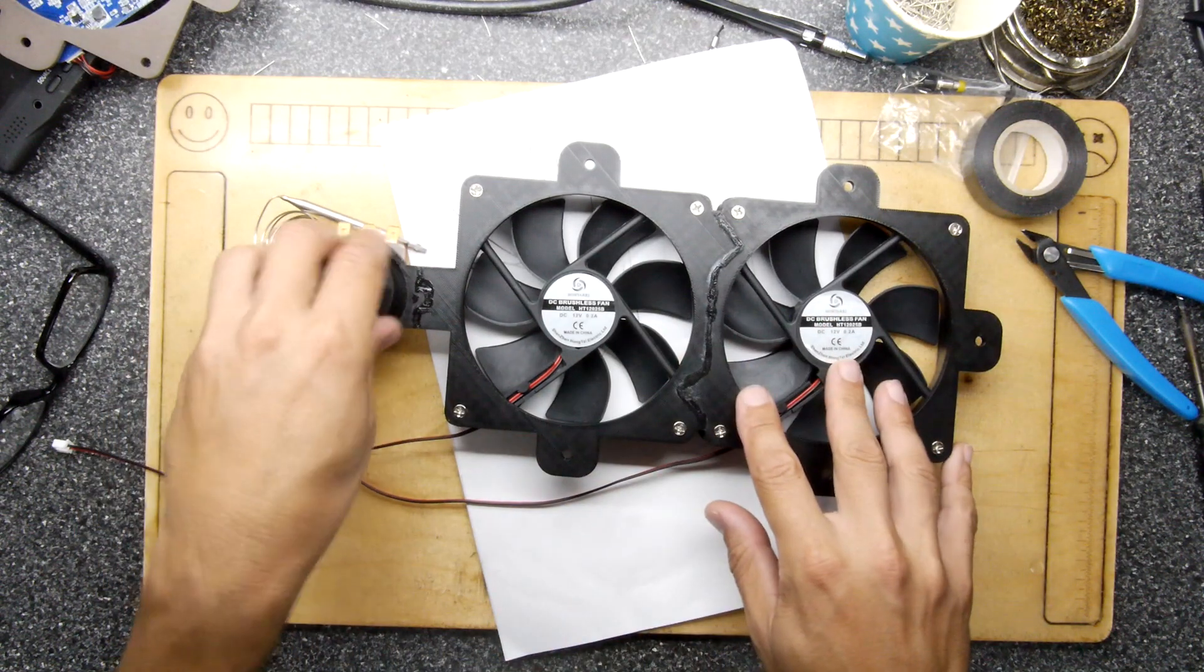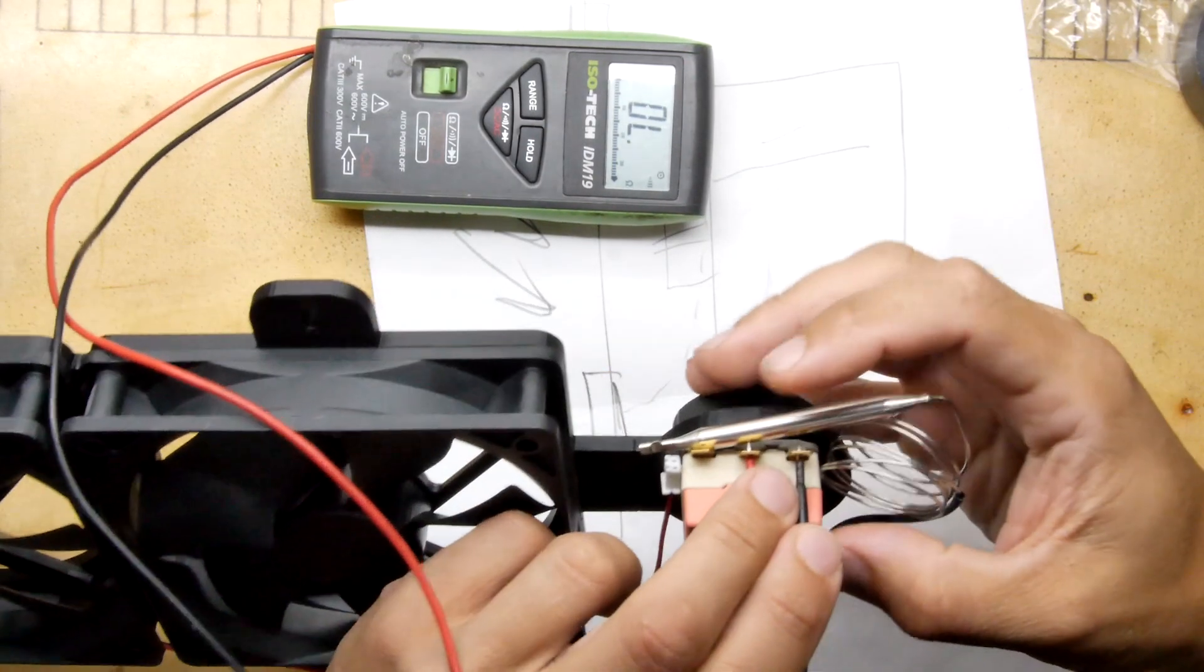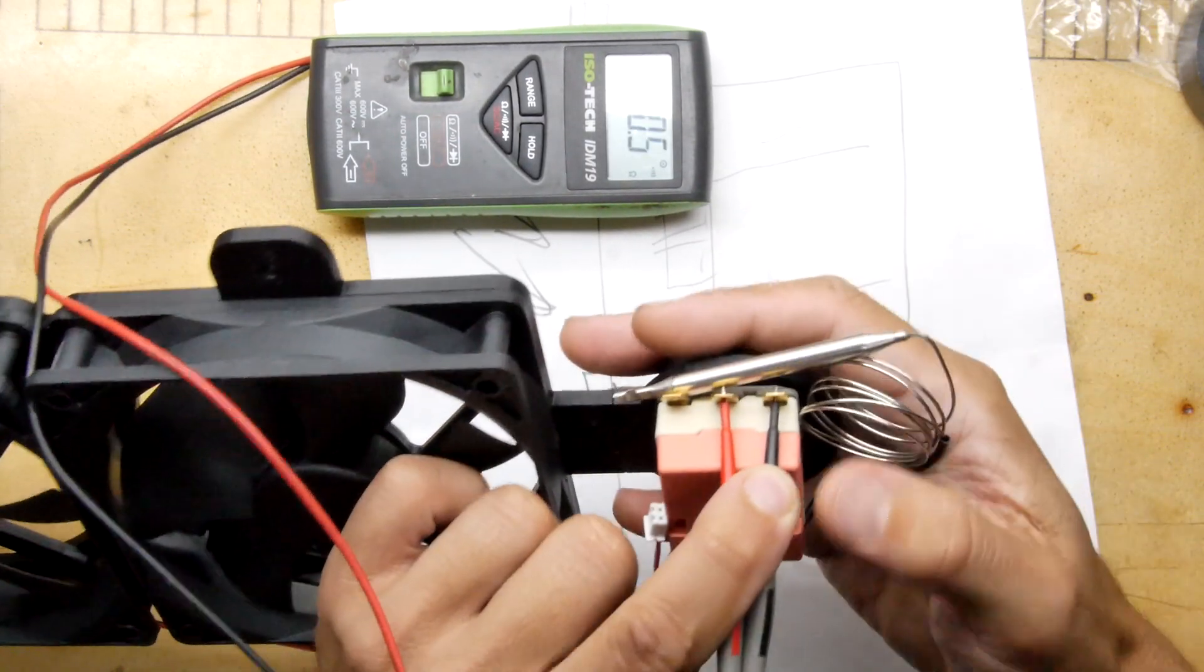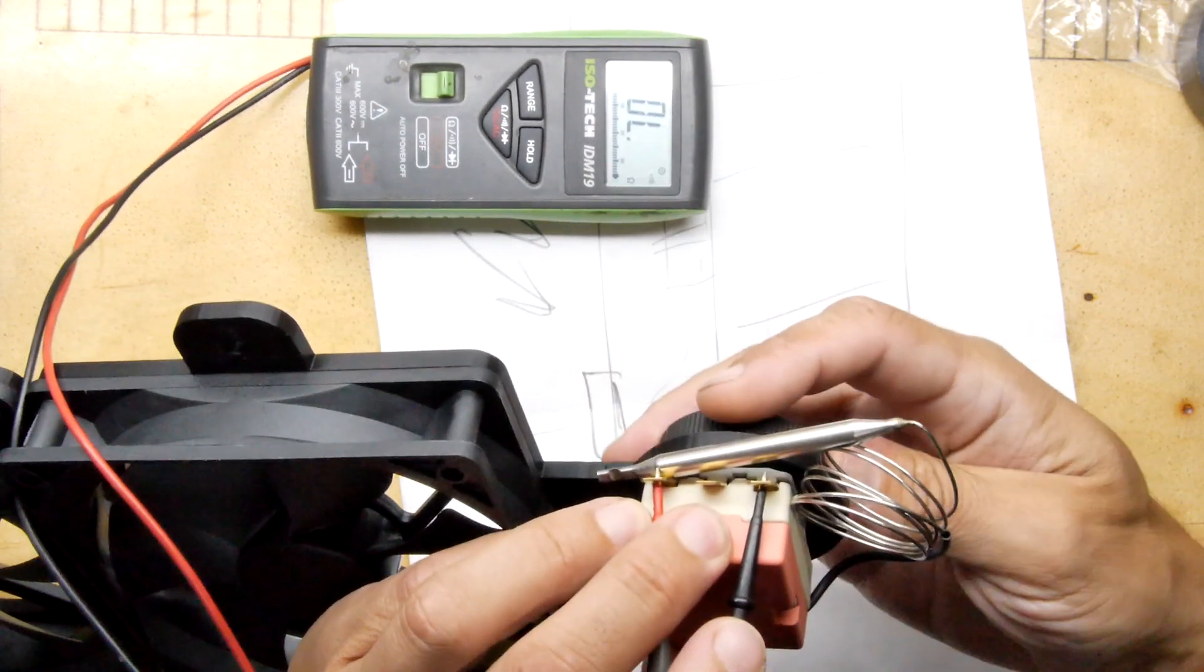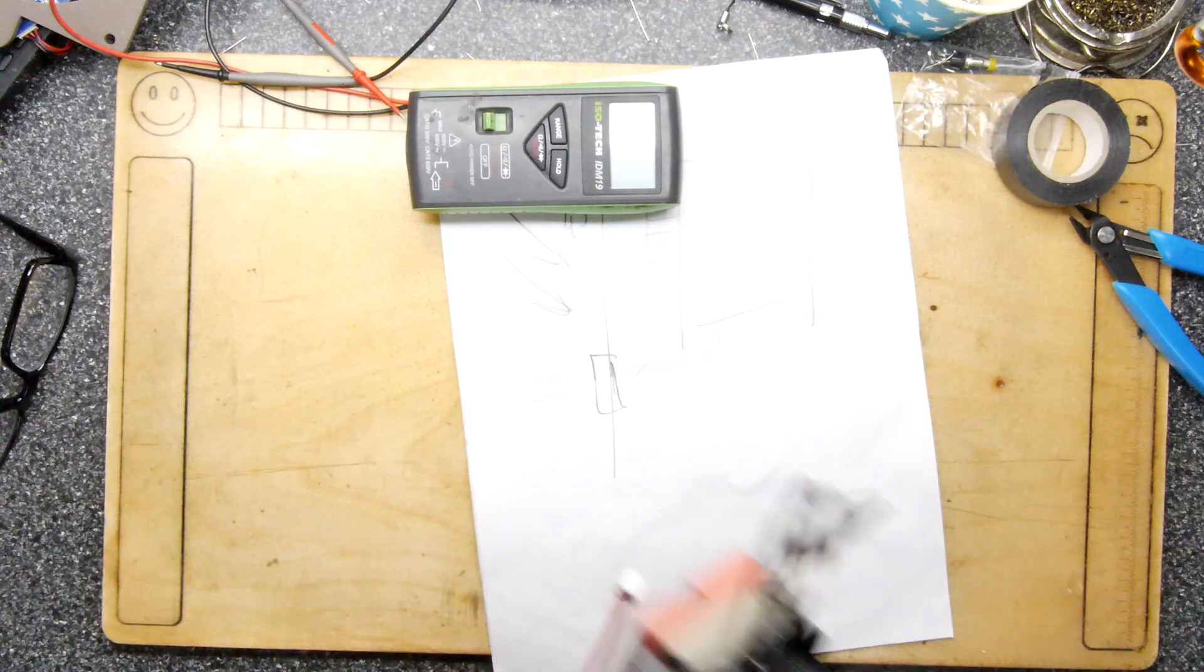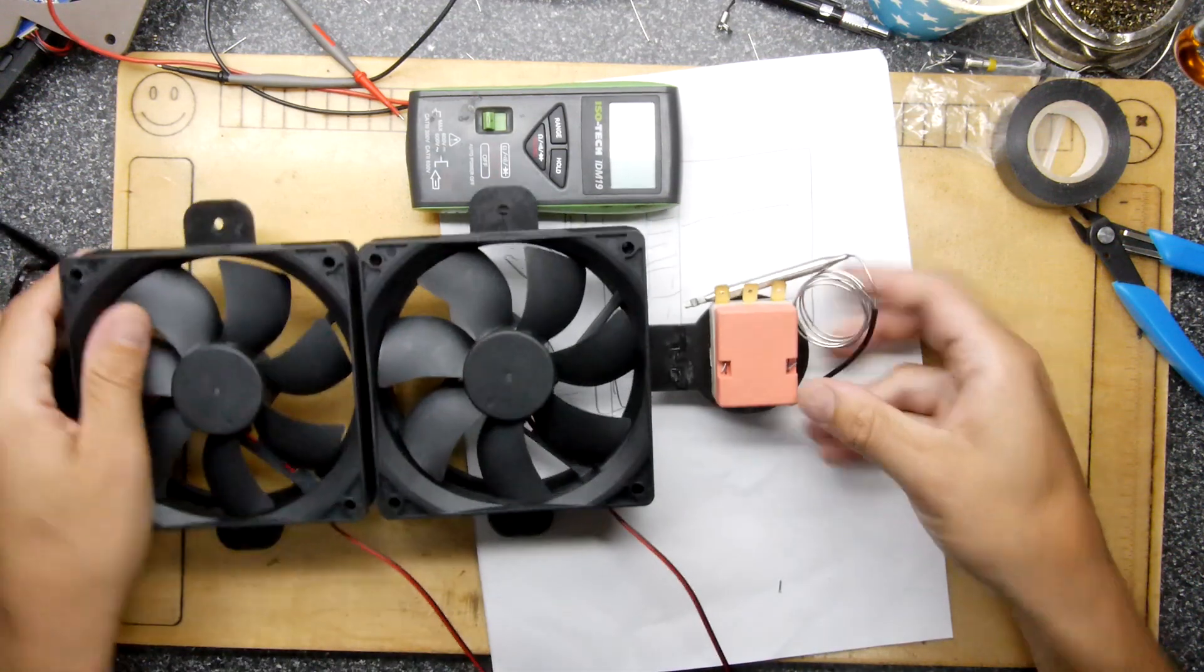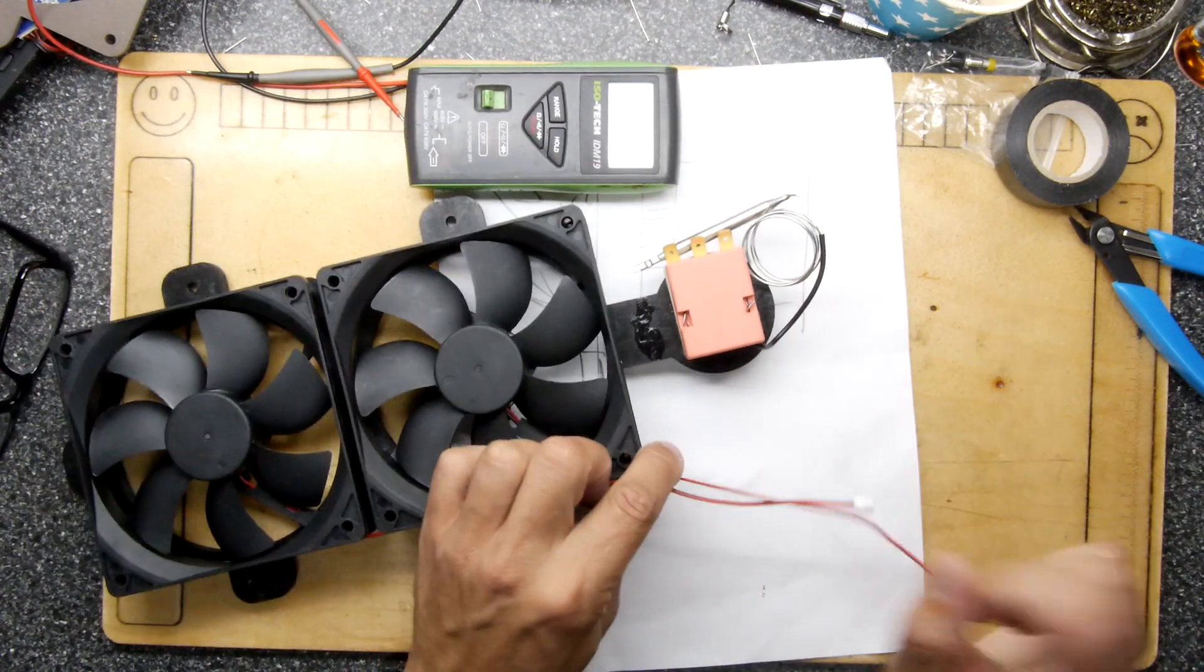So I'm just going to start cutting up and see if we can actually just do a little quick test on the bench. First things first, as a sanity check I've got a meter in continuity mode and I've put it on two of three terminals. We should hear a click, there we go, and that's them coming on. Now if I move this to here so between one and the common rather than two in the common, it clicks the other way. So you actually have a set of normally open contacts and a set of normally closed contacts and you will want them the right way around to make sure you're switching the appropriate way.